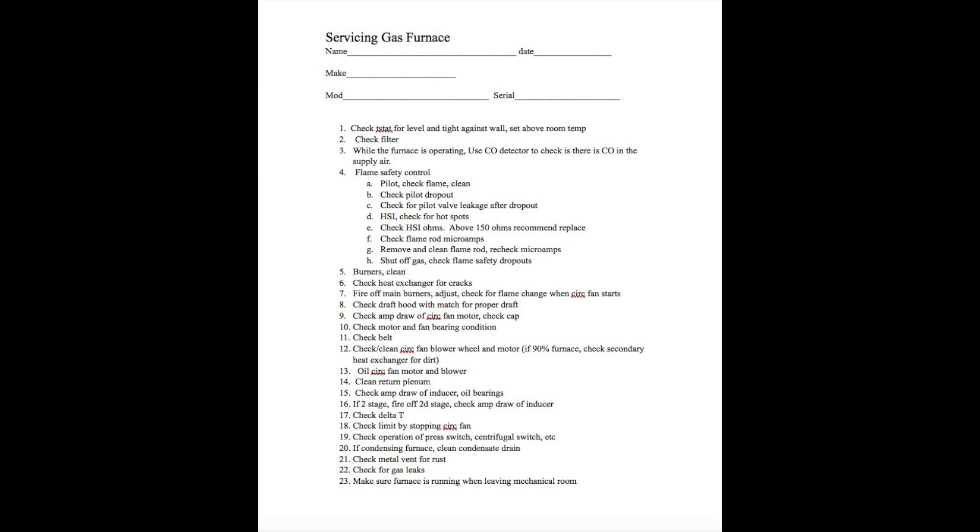This last one, make sure the furnace is running when you're leaving the mechanical room. This has gotten me in more trouble than probably any other part of this. When you put everything back together, you've got to make sure it's running. One of the big common ones is you put the fan cover on and there's a shutoff switch when you take the fan cover off. And if you don't get the fan cover back on right, then the furnace is not going to run. So make sure the furnace fires off and you haven't left a gas valve off or a gas cock or flame rod wire off or something like that. Make sure it's running and the fan is running when you leave the mechanical room. That's pretty much it. I will have all these little video references up there that may help if you get stuck in the middle of this. I hope this thing helps.